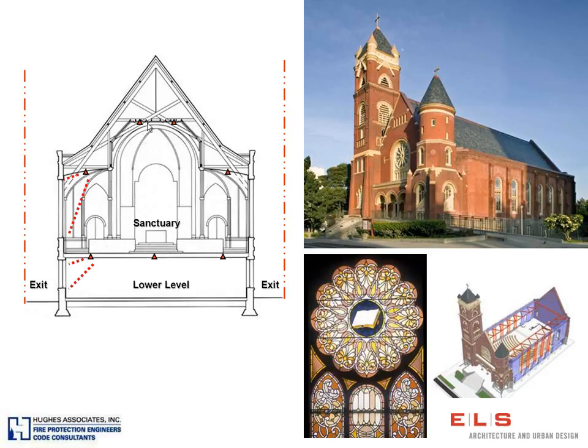So working with Cheryl, we designed a sprinkler system that we would install within the building and also be able to protect the art glass windows. And in that sense, since the fire could have come from within the building, protect the exit way on either side of the building. And that kind of vocabulary for keeping the interior and exterior of the building was important through all the systems, because as you might have expected, this was an unreinforced masonry building. And within these walls, we actually used a center coring system to preserve both the interior and the exterior.